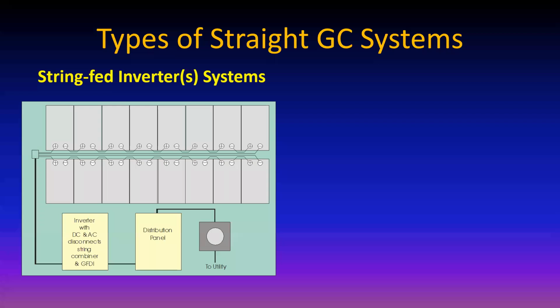The only problem with this particular system is there's pretty high voltage DC right at the input of the inverter. And that's where the rapid shutdown system comes in, and that's incorporated now in most systems right at the module level. But that's not shown on this basic diagram. Notice the line from the disconnect goes to the bottom of the distribution panel. The idea is that you normally connect to a distribution panel with a backfed circuit breaker that is on the opposite end of the bus bar from the utility feed. And we're going to look at that in more detail later on and see why that is.